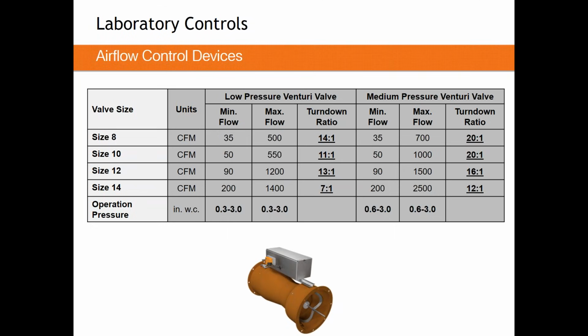So we read the first part similar to the others. It can go from 35 to 700 CFM, giving it a 20:1 turn down ratio. We're going to come back to that when we talk about energy a little bit later. It can achieve anywhere from that minimum flow to maximum flow, anywhere between 0.6 inches and 3 inches. So if you have 0.6 inches of pressure drop, you can get 35 CFM through your valve. If you have 0.6 inches, you can also get 700 CFM out of your Venturi valve.